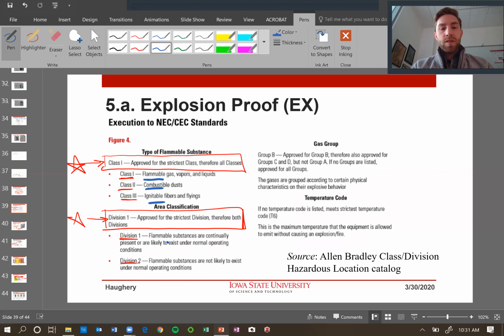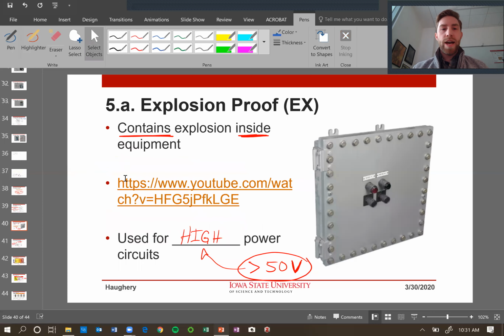And then we have the divisions, which is whether the flammable substance is continually present. So the divisions is how often those materials occur, right? And so usually the higher the class, the more stringent that environment is, the more careful we have to be in designing our electrical equipment. And the way to do that, we can have explosion-proof equipment, where it contains the explosion. If there's a spark inside a piece of equipment, it will contain that explosion. We can watch this YouTube video to see one of those explosions being contained inside of a really, really heavy-duty enclosure. This is for high voltage, usually above 50 volt circuits.